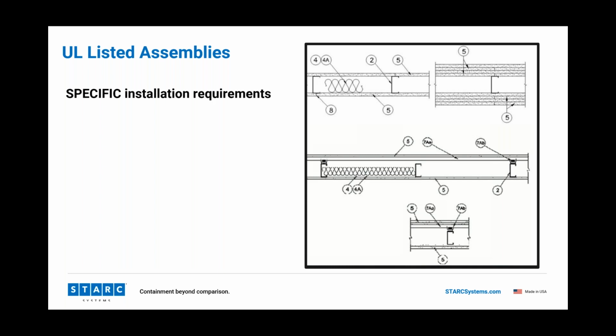It has requirements for how the drywall is installed. Let's just use a 2-hour wall, for example, with two layers of sheetrock on each side. The seams cannot overlap, and the screws have to be screwed into a certain depth. It has to be specific. So one great example here is I was working in an existing hospital built in the 70s, not fully sprinklered. So I actually required a 2-hour barrier to be built between the occupied area and a construction area.